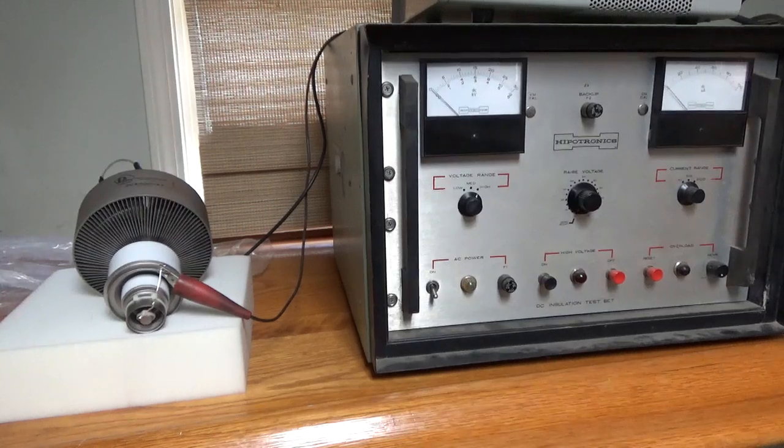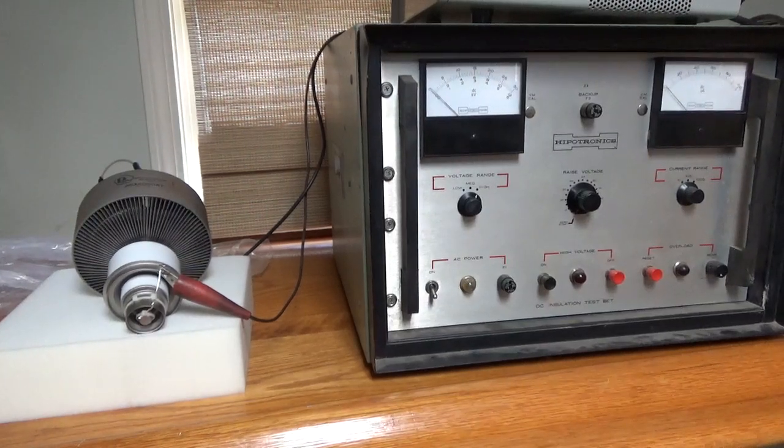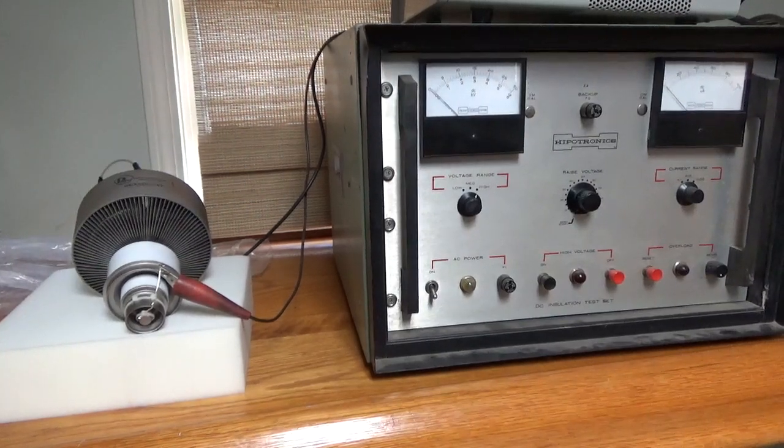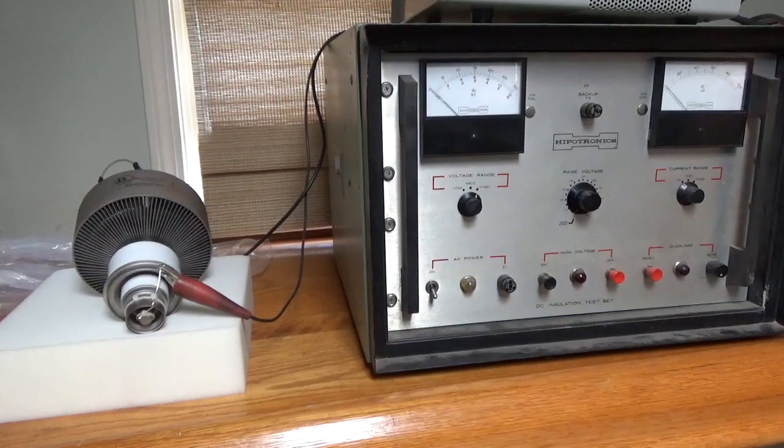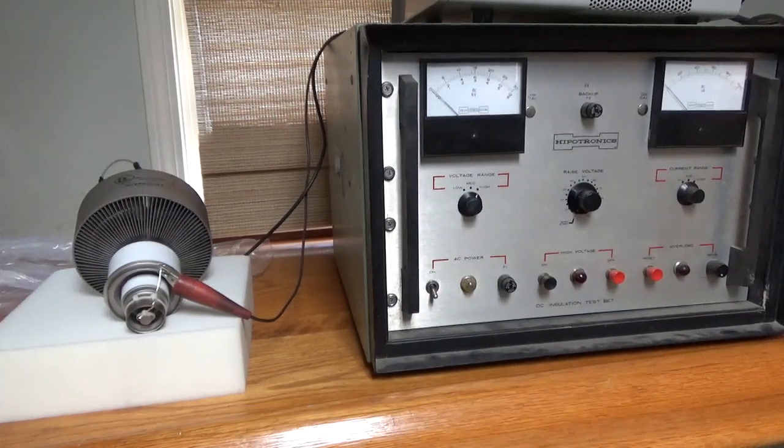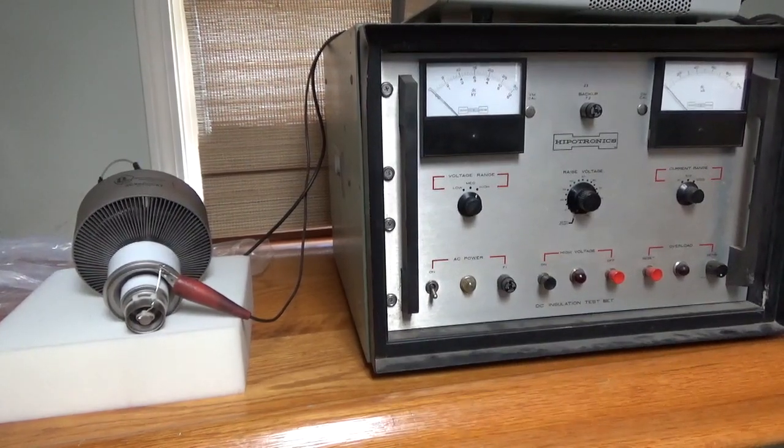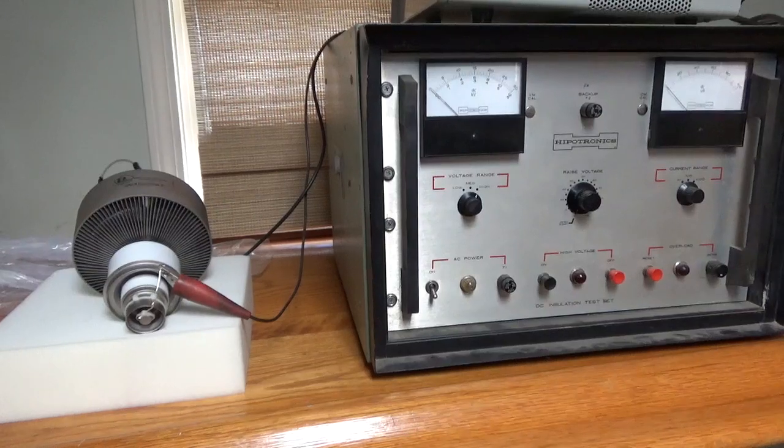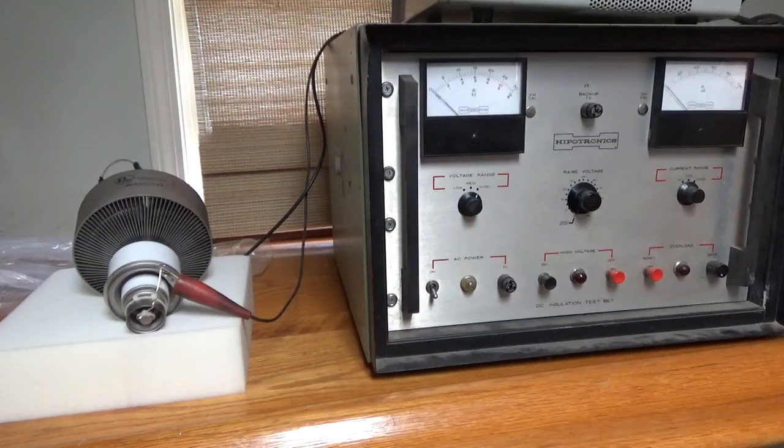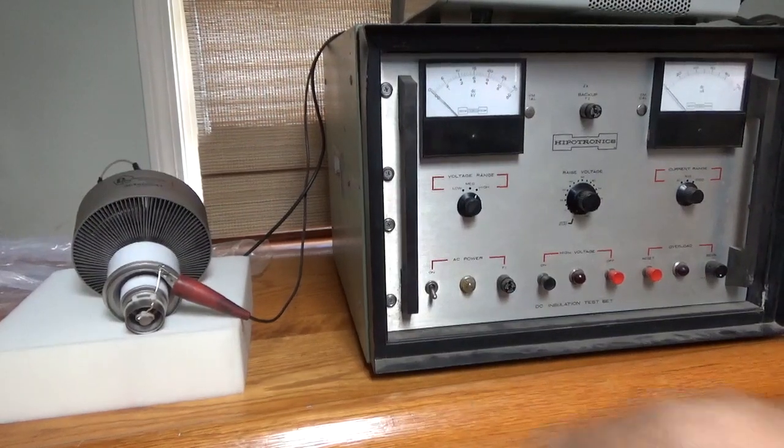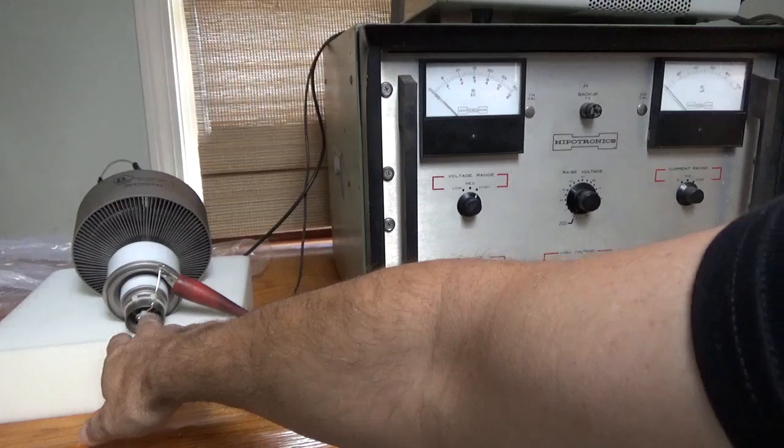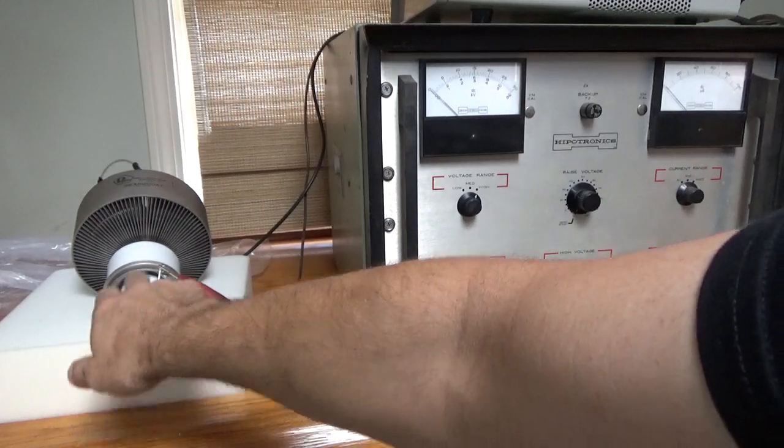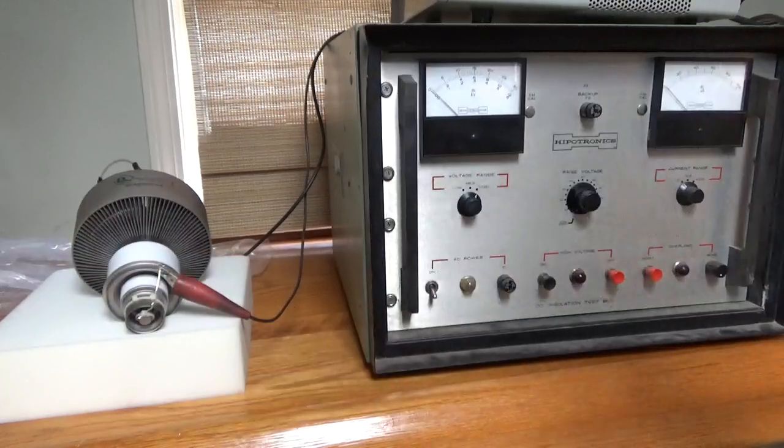Okay, so this tube should Hypot above 20kV, but I'll do it to 20kV DC. As you can see, you always want to attach the elements together. You've got the filament, both sides of the filament tied together, and it's tied to the grid.